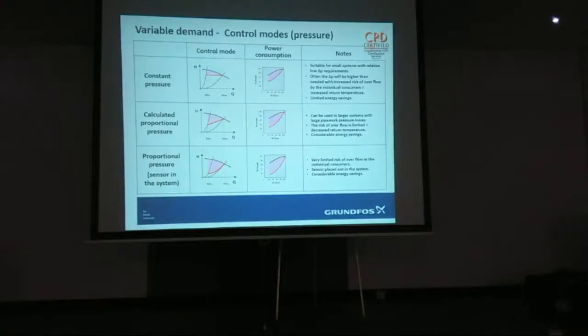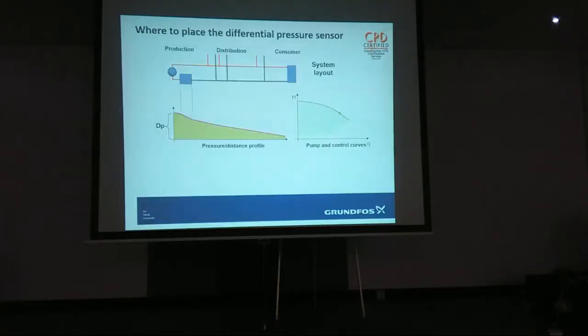A number of people put single point pressure at the top of a riser. When it's cold, it's measuring one pressure. When it's hot, it reads another pressure. They don't work. You need differential pressure.